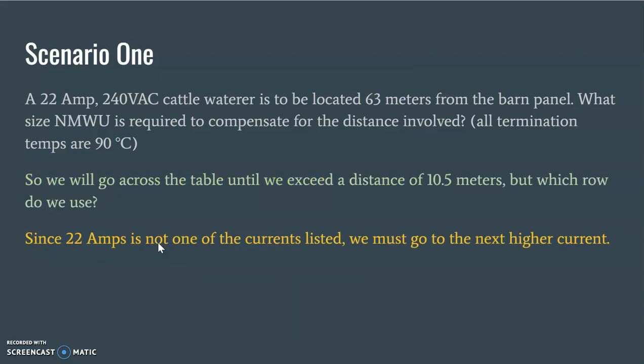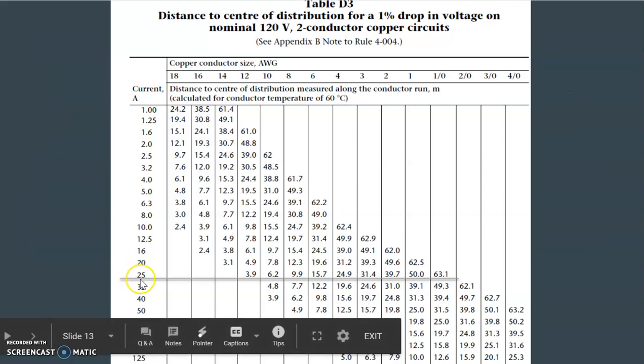So as I mentioned before, we're going to go across on a current row and try to find a distance that exceeds 10.5 meters. But which row do we use? So since 22 amps falls between 20 and 25, we don't want to go with a lower current. We actually want to go with the higher current to make sure that we're safe. So we're going to go to the next higher value, which should be our 25. And that's what we see here, 25. It's roughly underlined 25 amp row here, and we go across until we exceed 10.5. 9.9 is close, but not close enough, so we go to 15.7, and that takes us up to a number 8.